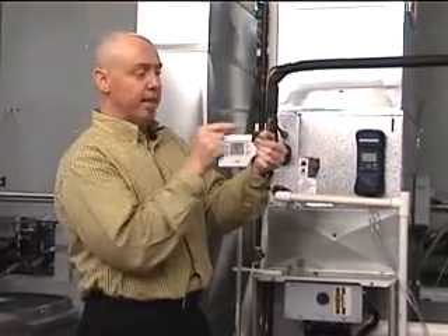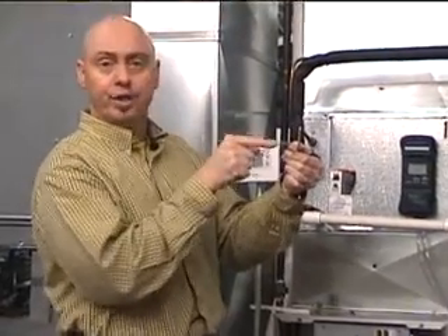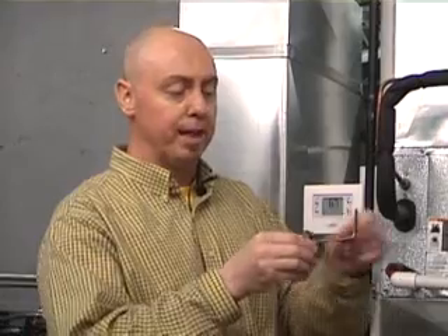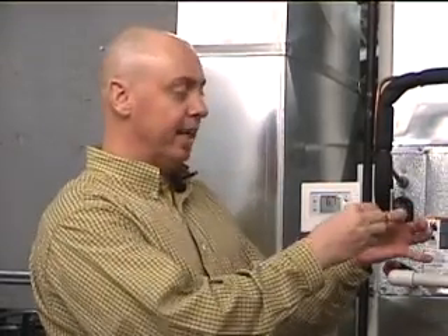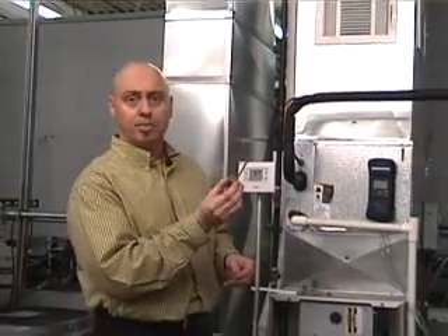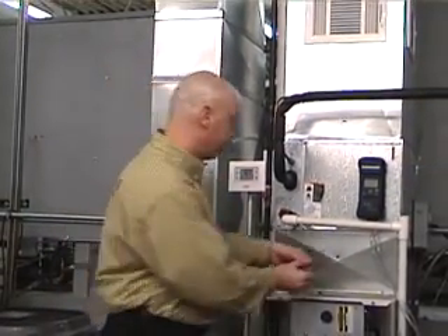Airflow is going this way. Inlet sensing probe is 90 degrees to the airflow. So I recommend you use something like this, because if you use a regular probe that has a hole in the end, when you stick it into the duct, if it moves up or down or left or right, it will change your readings considerably. So if you want to be as accurate as possible, use something like this as a static probe.